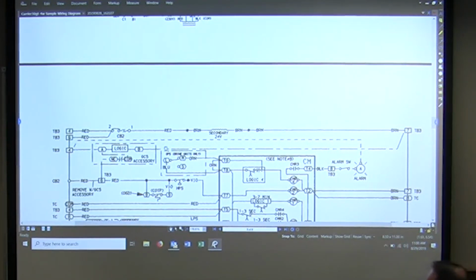Now, the other thing that was mentioned is you could put a coil across 1 to 2 right here. What would that tell you? It would only indicate if the transformer is live and the breaker is true. Yeah, so you will potentially backfeed through this, and you would have a voltage drop across that if it opens, if you get a trip. I probably wouldn't do that because it'd be a little more confusing, but you could do that. That would be another option.